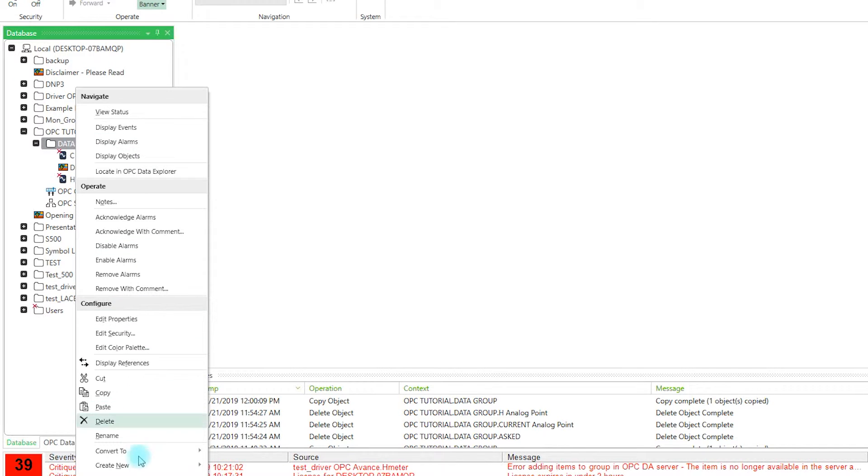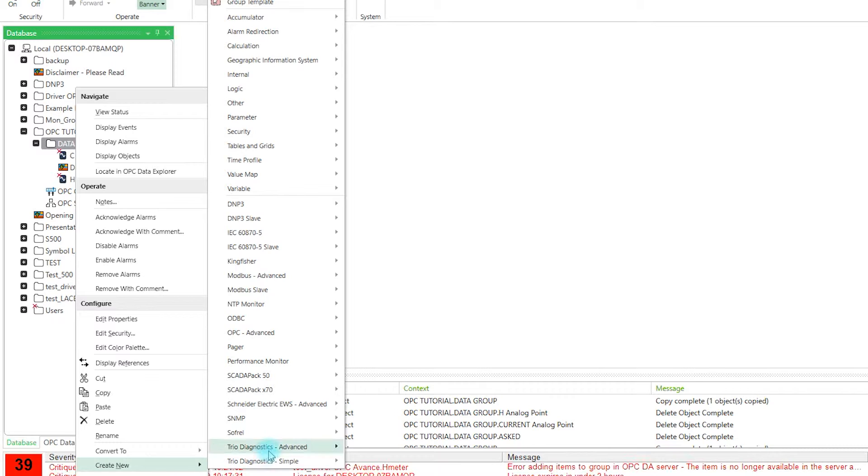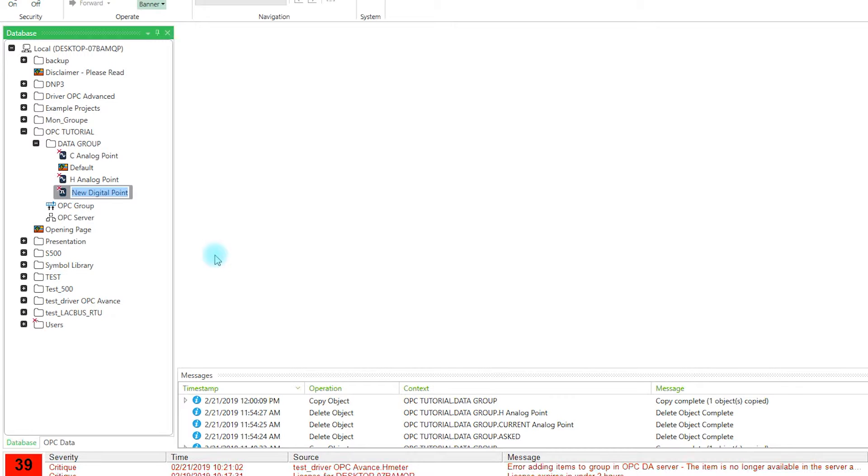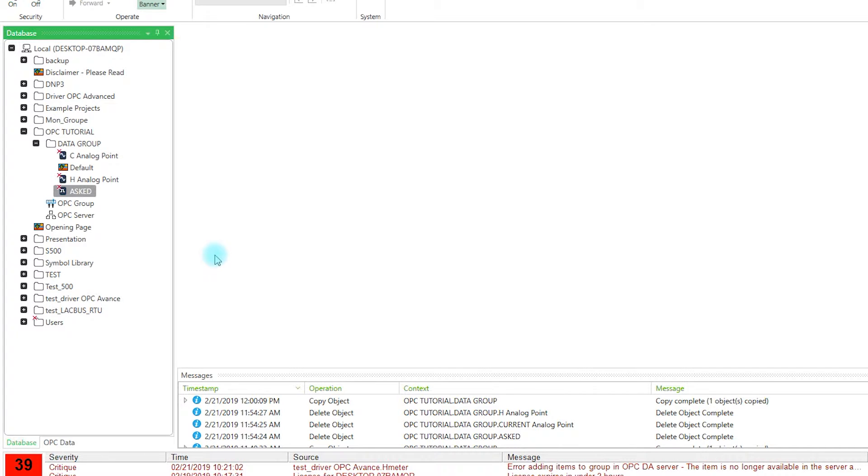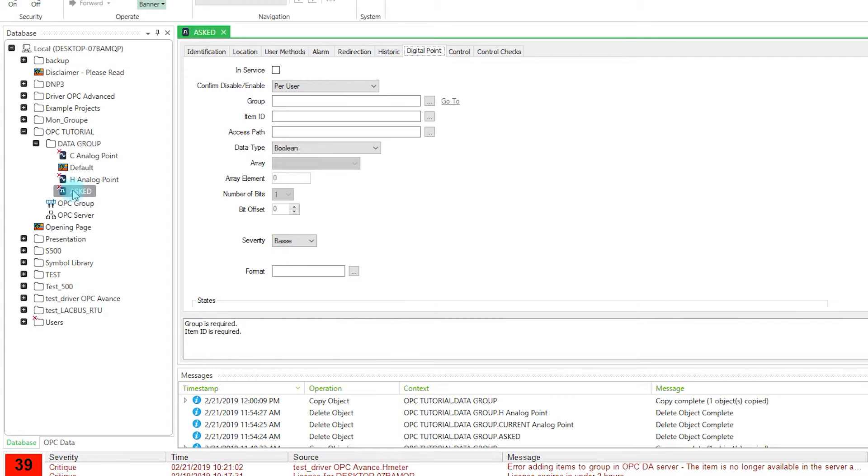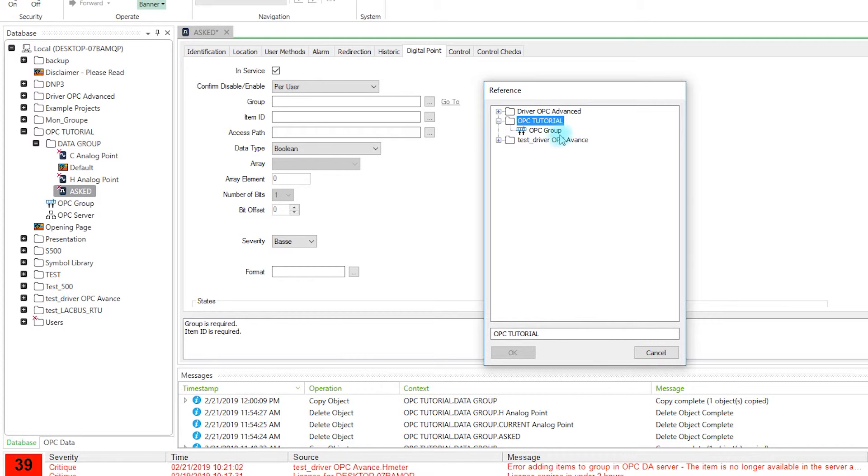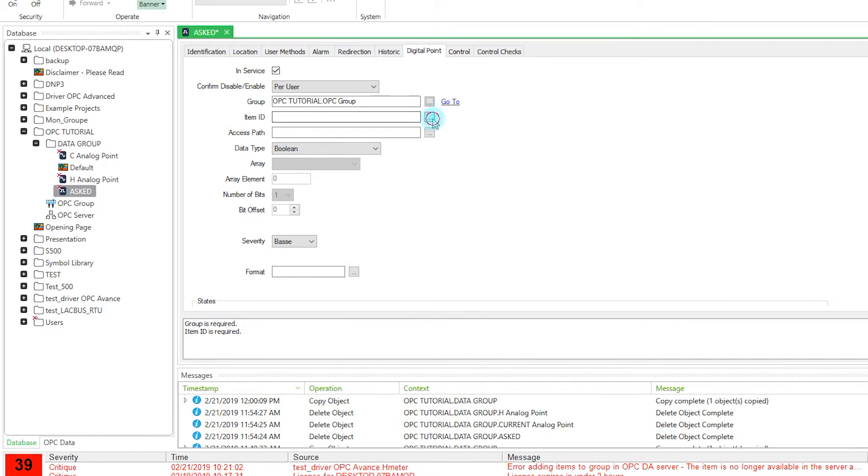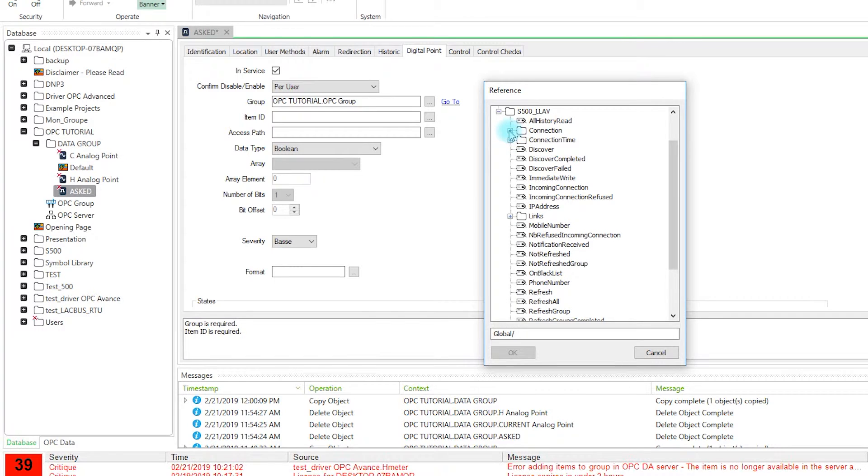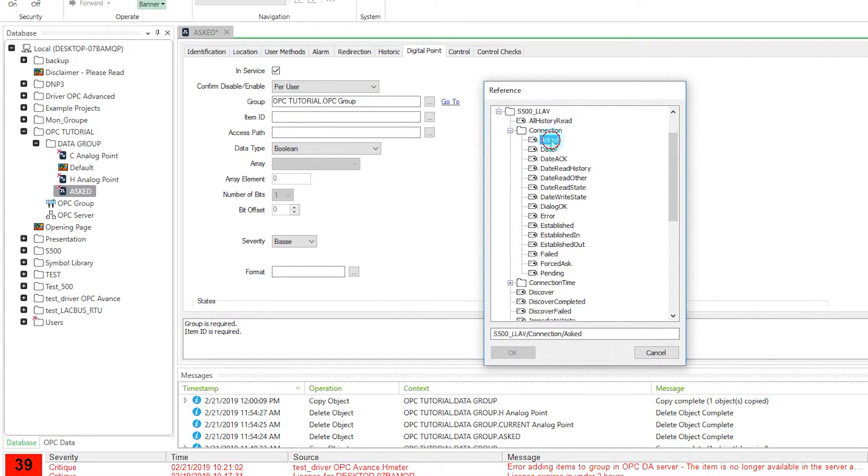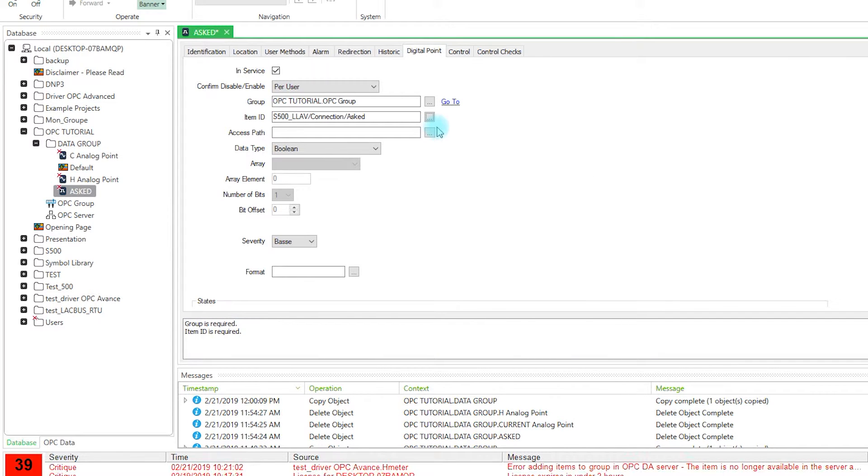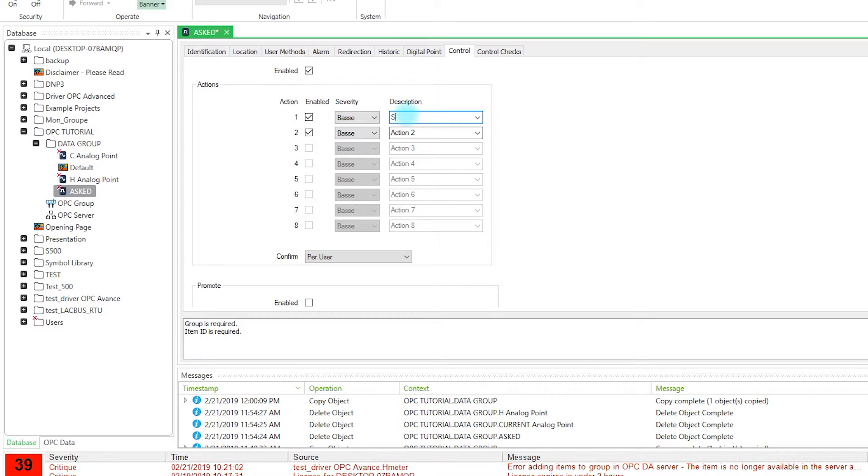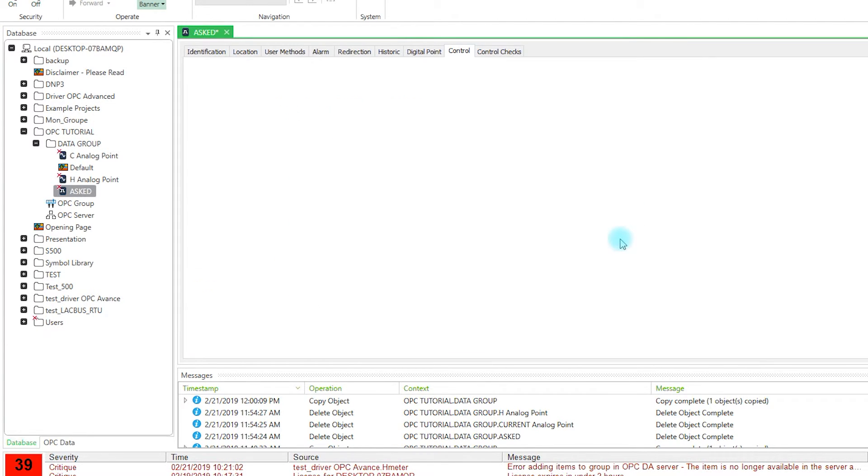We will also need a digital point for the item asked. This item is necessary to start the communication. So we will tick in service, select the group, and you will find the item id in the RTU connection and then asked. In the CTRL tab you have to enable two actions. One to stop the communication and one to start. CTRL S to save.